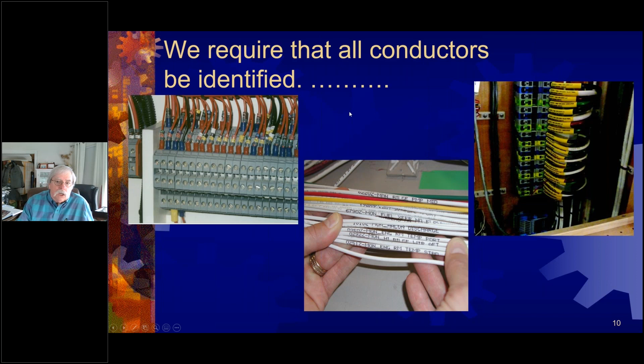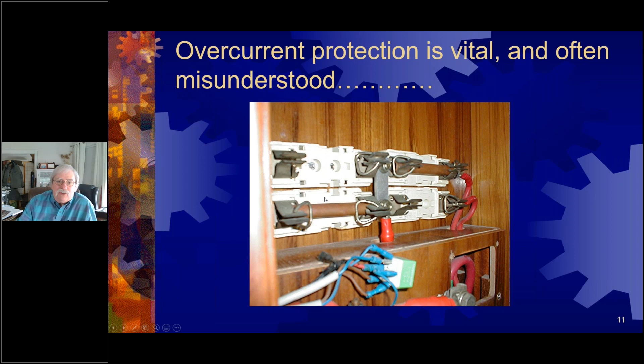Overcurrent protection is vital and often misunderstood. This particular photo comes from a boat that was getting ready to set off on the Transpac race out of California going to Hawaii, and that 1/2-inch copper water pipe is a great fuse. You'll never have to worry about it tripping or blowing. It's one of the scariest things I've ever seen in terms of how to deal with overcurrent protection. But that's real. That wasn't staged.